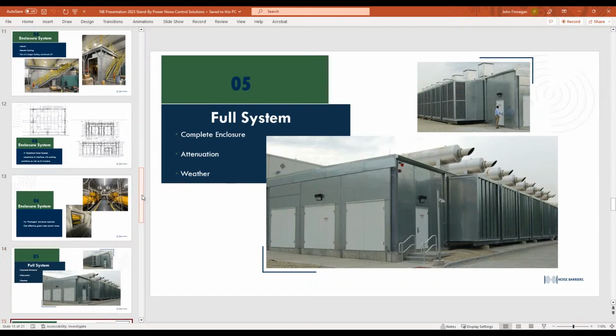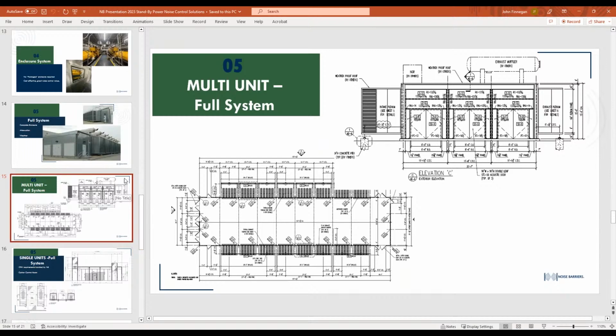We take care of the weatherproofing on the roof. This is just a simple drawing showing how we lay this all out. We do all the engineering drawings. Each gen set sits in each one of these bays, and we provided the entire structure, the structural steel, the panels. We designed the inlet, which comes in through... I've got another drawing here, nope I don't, I'm gonna move off that. So this is the inlet plenum, which you see right here in this picture with this guy standing next to it. That just came in through very basic weather louvers, and then it's fed through the silencers, dampers.